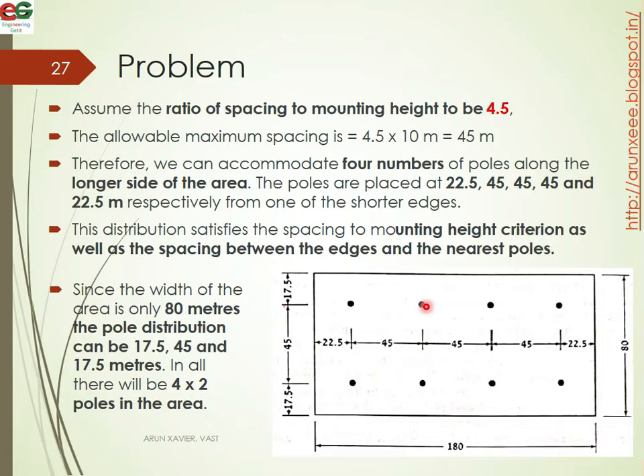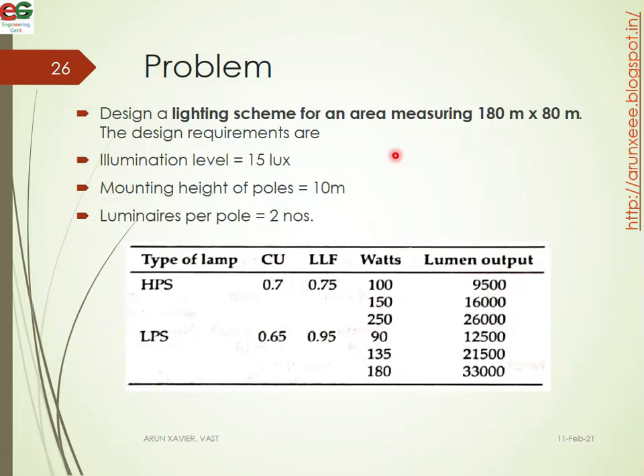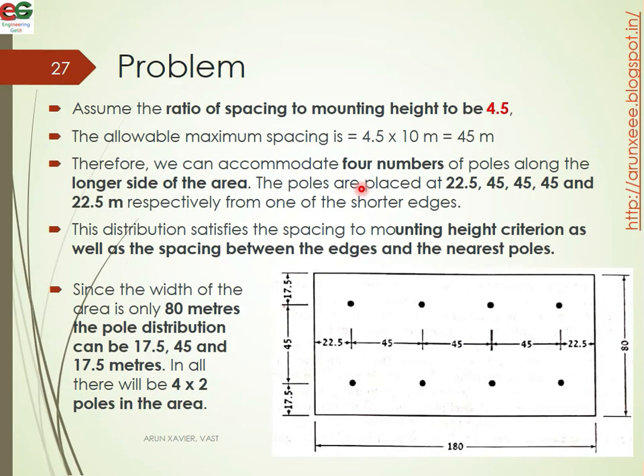The ratio of spacing to mounting height must not exceed 4.5. The allowed maximum spacing is 4.5 times 10 meters, since the mounting height is 10 meters. Therefore, the maximum spacing is 45 meters. Based on this, we can accommodate only 4 poles along the longer side of the area.